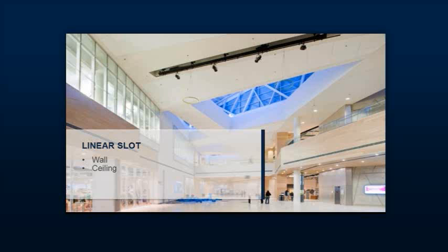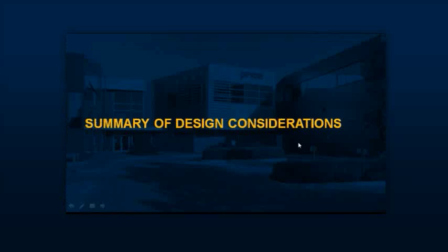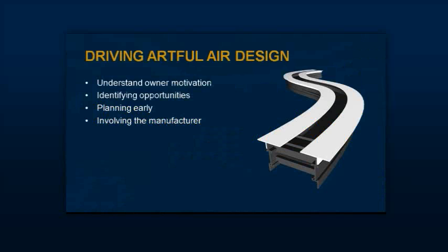So how often is it? Most buildings don't require a full-blown mock-up. It's when you get on the cutting edge or near that cutting edge, like that chilled beam inside a patient room example I just gave you, that we want to assure ourselves that we have achieved a proper design for thermal comfort. And we were one of the people stressing we wanted to do this mock-up. I'll be honest with you, I was going to do this mock-up whether the end user wanted to or not, simply because I always learn something from these mock-ups, and I love the interaction between you and me. It's always a learning experience.